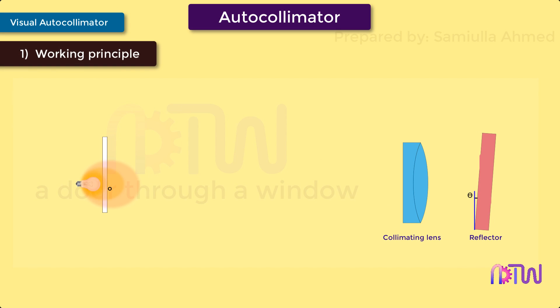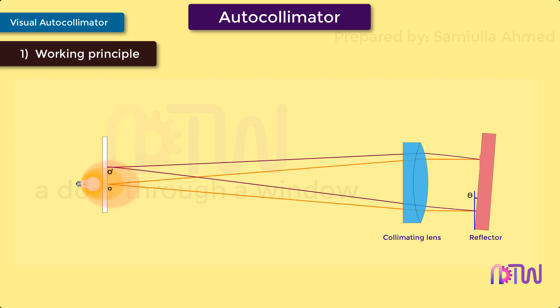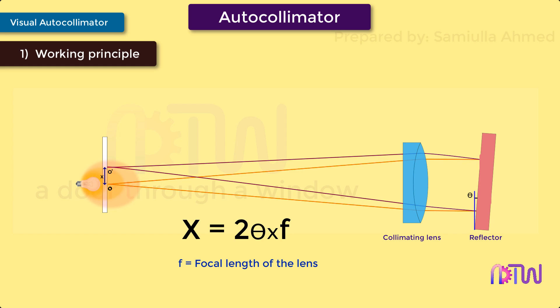If the reflector or surface is at an angle theta, the incident rays are reflected at angle 2 theta, and the reflected rays fall at point O dash. By knowing the distance between O and O dash, which can be denoted by X, we can find out the angle theta using the relationship: X = 2 × theta × F, where F is the focal length of the objective lens. This is the working principle behind the autocollimator.